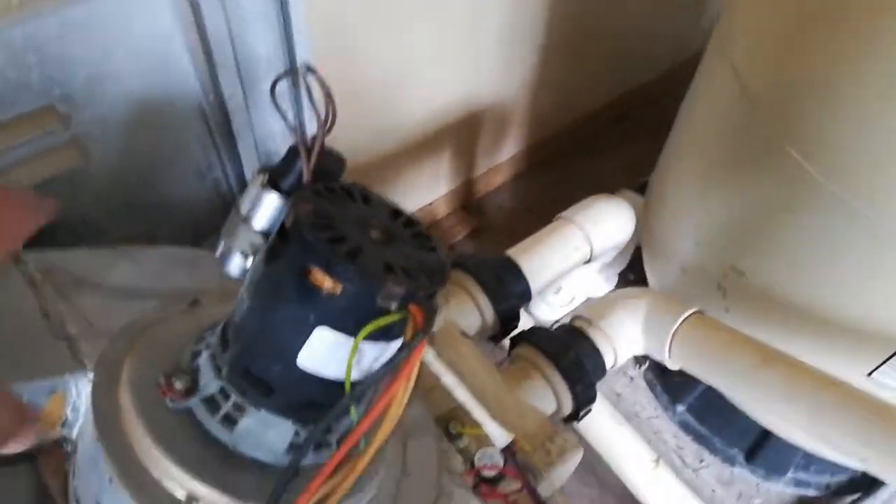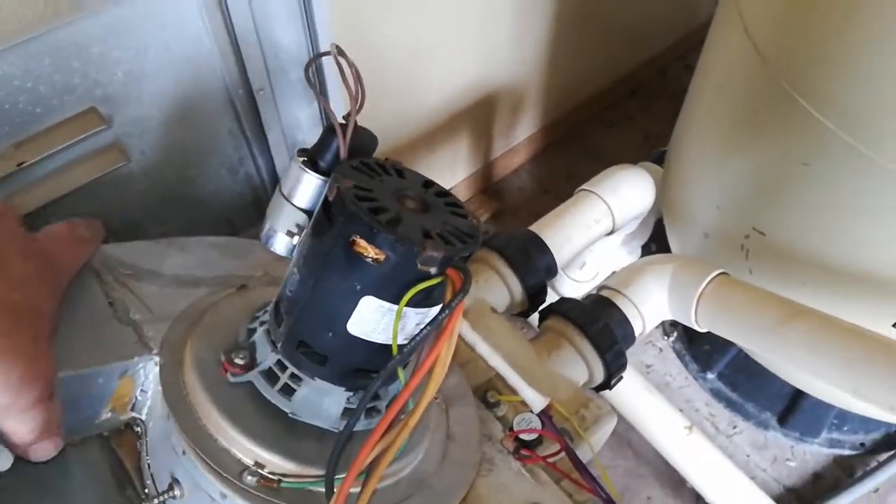I'm not sure what you'll be able to see, but there's a plugged section in that burner. I tried to pull the whole top thing off and it doesn't work, so basically I pulled off this — there's a screw that holds that box in. There are four screws that hold the fan; pull the fan, disconnect the hose and the power.